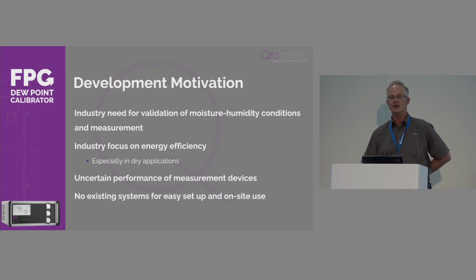Another reason was the uncertain performance of humidity and moisture measurement devices. Those of us who have worked in this field for many years know that in certain kinds of conditions, the sensors are not working very well at all. But unfortunately, there was no practical solution to confirm that, so we wanted to find an answer to that. And there were no existing systems. Until this product was introduced, there was nothing where you could actually calibrate a moisture sensor on site, which meant it's very difficult for engineers to validate the performance of their systems without very complicated moving of the product, sending it away, or going to a laboratory. So that was the motivation for developing the product.